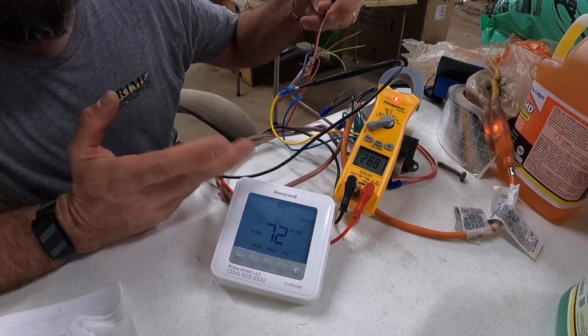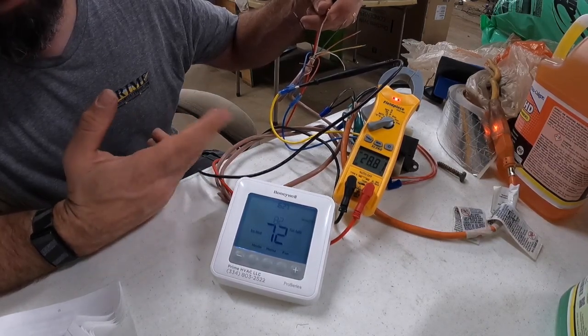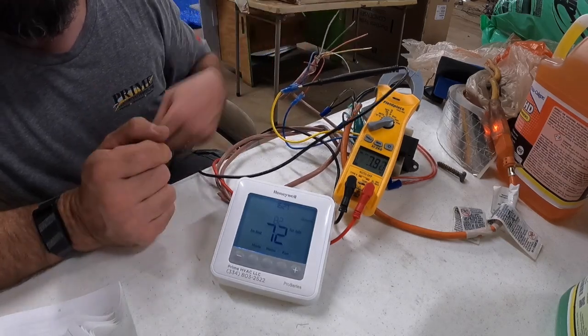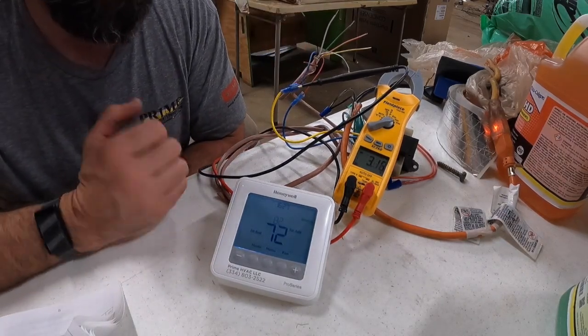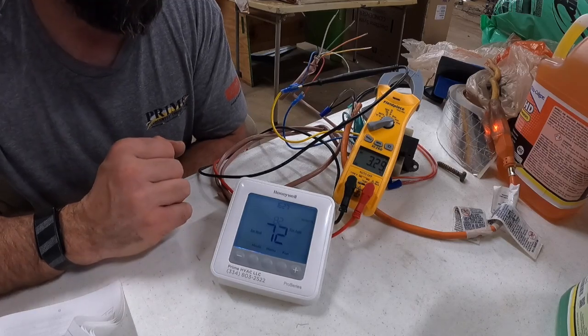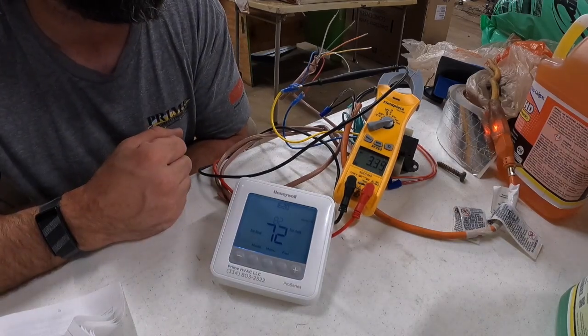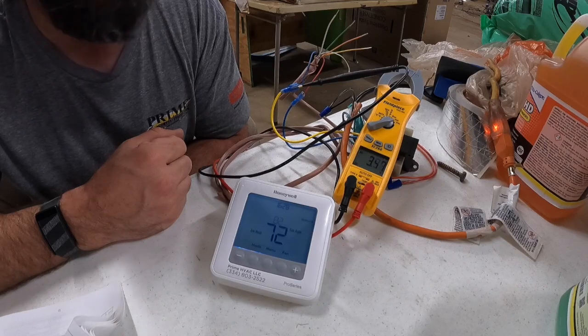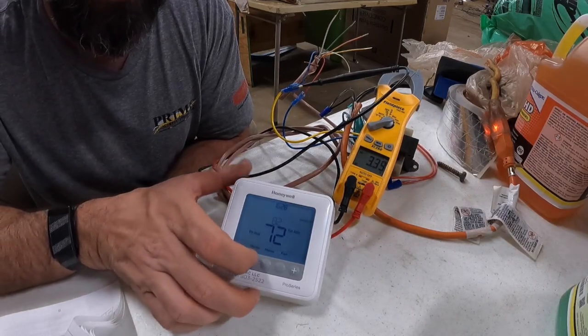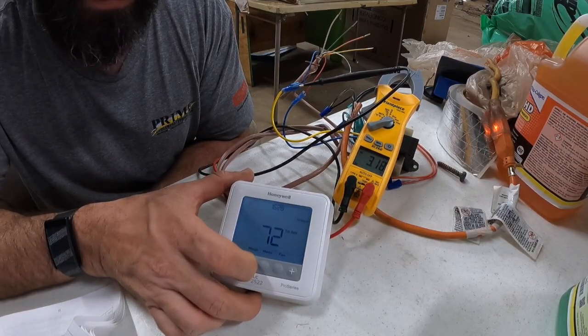I mean, we're getting the, oh, it is calling for white. So it energizes W and E on this thermostat model. On the Focus Pro, it just energized E. Some people stage the heat strips. Most of the heat strips that we install don't have stages unless it's in a communicating system.